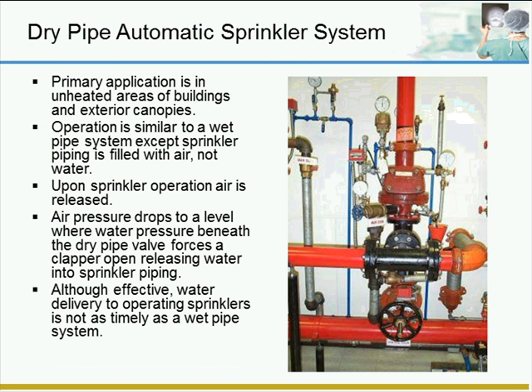This photograph is of a dry pipe sprinkler system. It is very similar in appearance to a wet pipe sprinkler system, where you see the alarm valve about halfway up above the black section spool piece of piping. That is the dry valve. From the dry valve below, we have water. From the dry valve above, the system is filled with air. This provides a delay in the water reaching the fire once the sprinkler head is fused. This type of valve is used in a pre-action system, which allows you more time in the event of a false alarm to get in and shut the water supply down, prohibiting water damage to delicate electronic equipment.